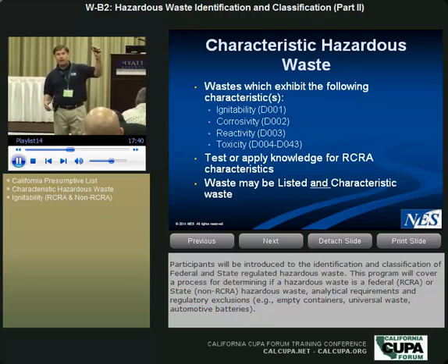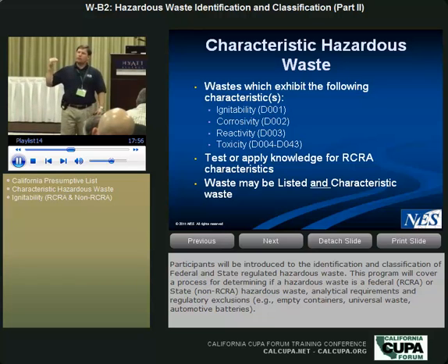We have state metals, we got federal metals. But once a federal metal is present above the regulatory threshold for being a hazardous waste federally, then it's captured by RCRA, and how that gets treated is subject to the federal requirements. So the cost of managing that goes up exponentially. But the receiving facility is going to be the one that imposes a standard on me. Hey, we want an analytical result of the metals.